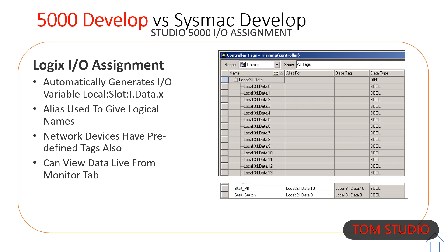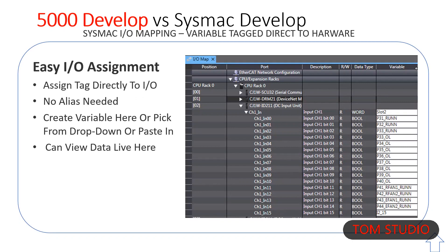Sysmac Studio's I/O mapping works and the AT address is automatically assigned. You can copy and paste these tags to a different module if I/O physically moves, which makes a nice I/O document when pasted in Excel. You can also set and force data here.